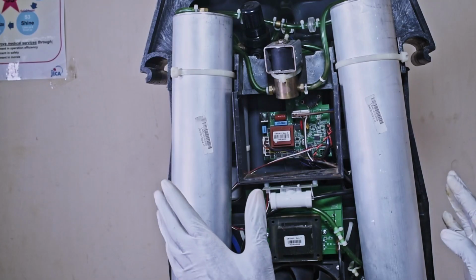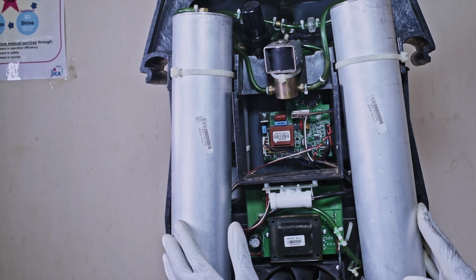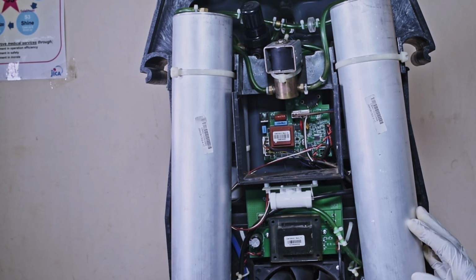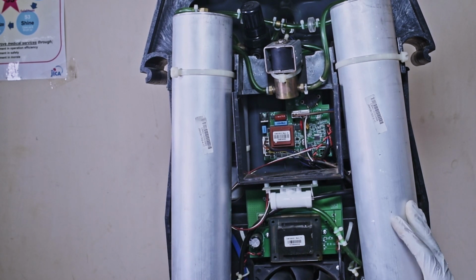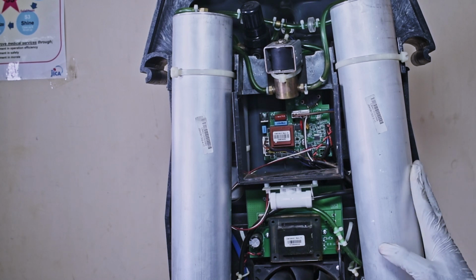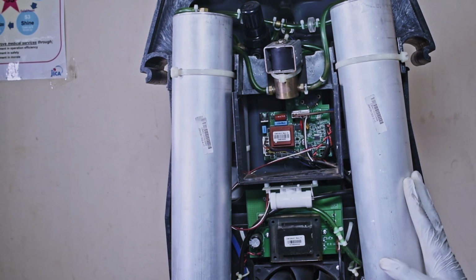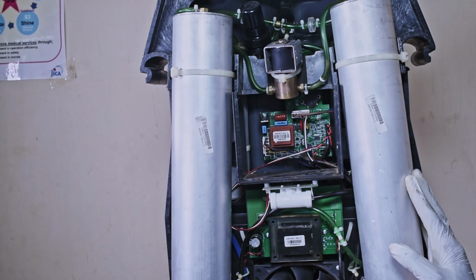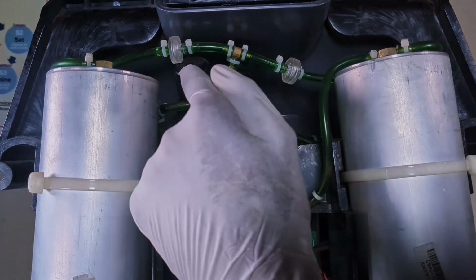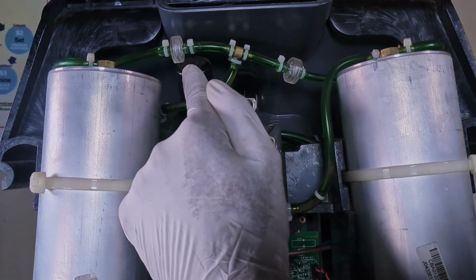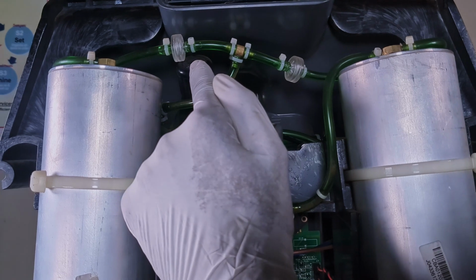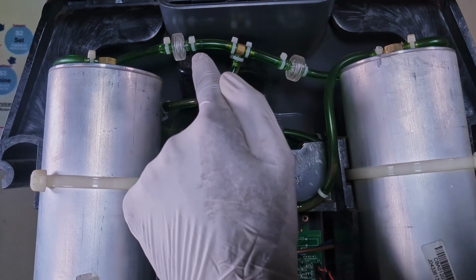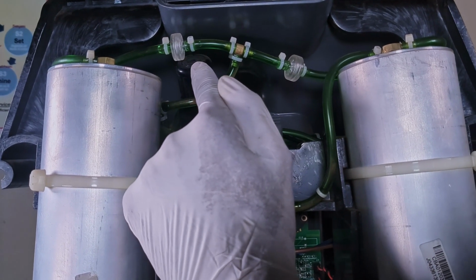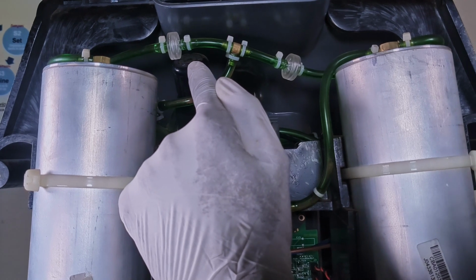Here we have 2 sieve beds. These sieve beds are used in the oxygen generation. They contain zeolite, which absorbs nitrogen, hence allowing oxygen to be concentrated. Here we have the pressure regulator. The pressure regulator is calibrated at 20 psi. It ensures that oxygen is delivered at a constant pressure of 20 psi.